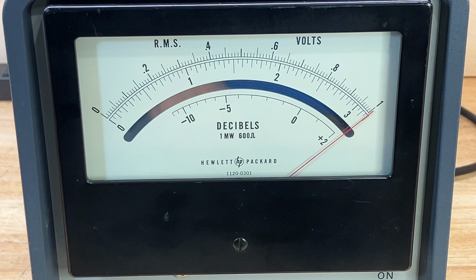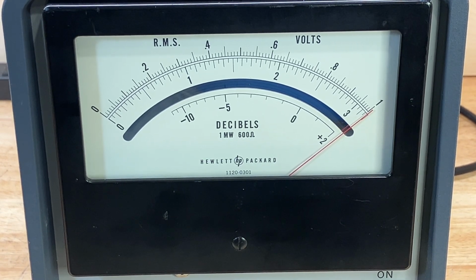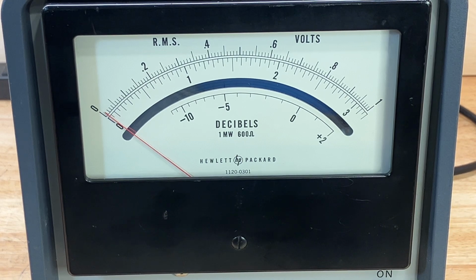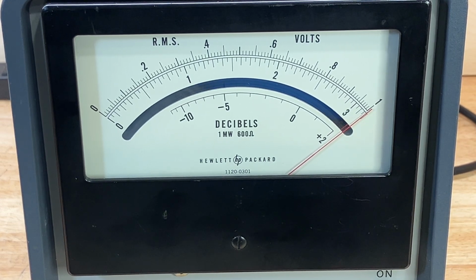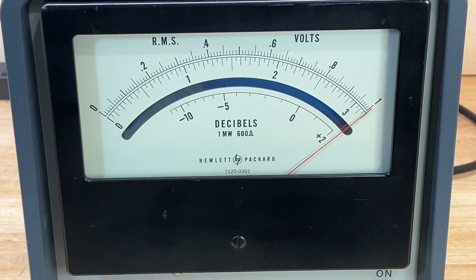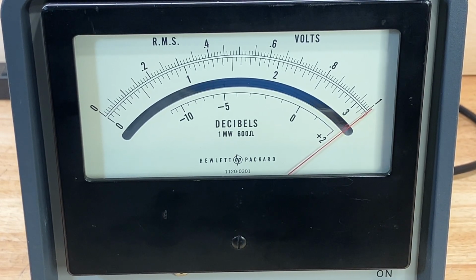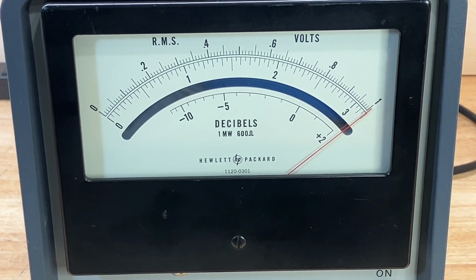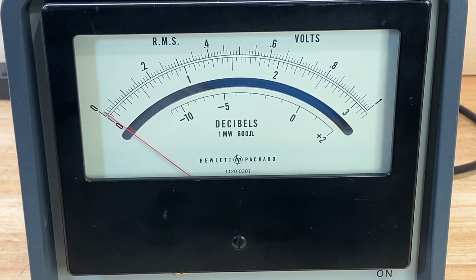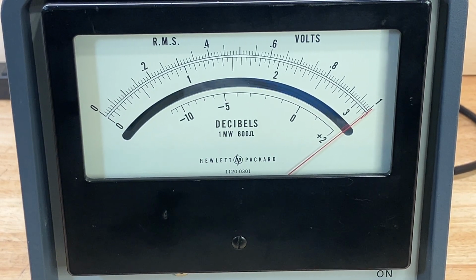All right, so after reassembling everything, I think I have fixed it. There it is with power applied, with the input applied. Let's turn it off, and it goes right down. The needle is no longer sticking. Actually, the instrument is reading about 10% high, so it's way out of spec. But I'm sure I must have bumped something in the calibration when I was brushing the dust out of the inside of it. I must have changed something in the adjustments. But I don't have the manual yet, so I'm going to have to wait for that manual to come in before I can redo the adjustments and bring it back into spec. But the needle is no longer sticking, so I fixed the biggest problem with this unit.